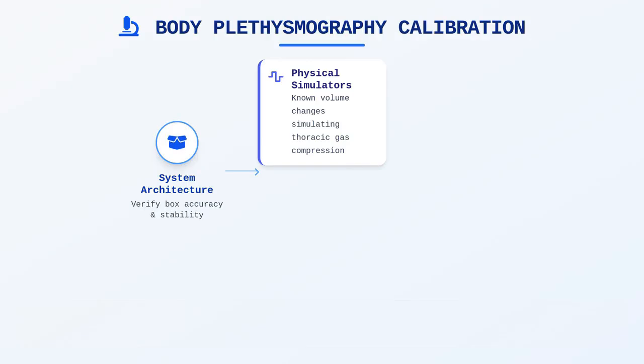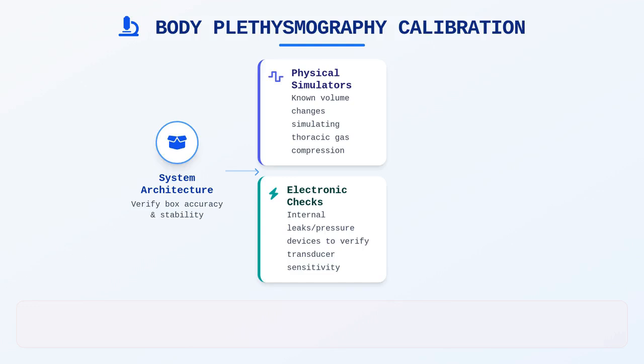Body plethysmography introduces a unique set of challenges because the entire system architecture, including the box itself, must be verified for accuracy and stability. To calibrate the plethysmograph, we utilize physical sinus wave simulators that provide a known volume change within the box, simulating thoracic gas compression and expansion. Alternatively, some systems employ internal electronic leaks or pressure-generating devices to confirm that the transducer sensitivity reflects physical reality.